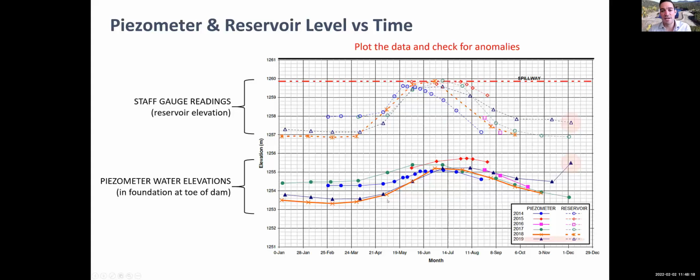And yet, if your piezometer came down as expected, and then all of a sudden you see a high value, I'd be pretty confident that there's either an error in data collection or we might have a problem. So nine times out of ten, someone probably transposed the numbers, or read the wrong value on their tape measure or something like that. But that's something I'd want to confirm and not just leave till the next spring, right?